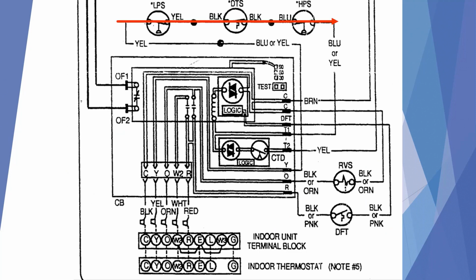As you check through the safety circuit and check the safety switches to make sure that they are closed, you don't want to forget where they plug into the control board. Many times technicians check out the switches and they're closed and they say, well, there must not be a problem there. But then they go and check the plug where the safety switches plug into the circuit board and find that a pin is loose or is not making contact where the plug goes into the board. So don't forget to check the plugs on these systems either.